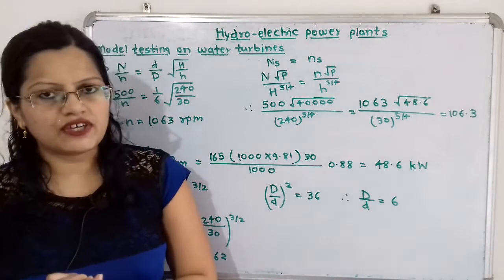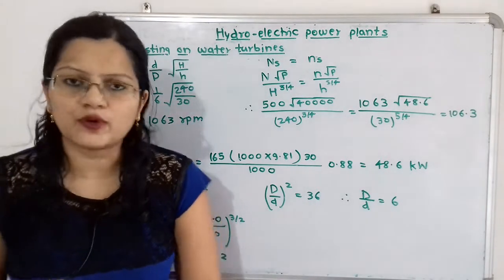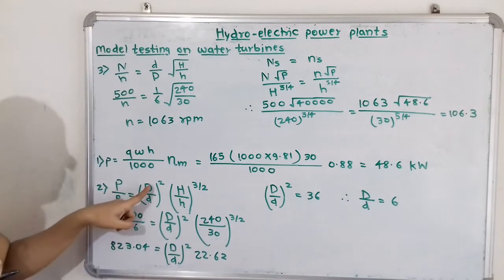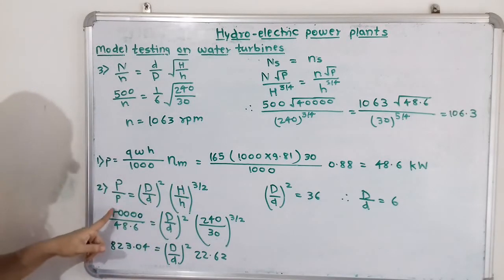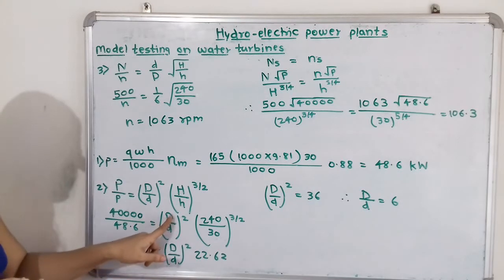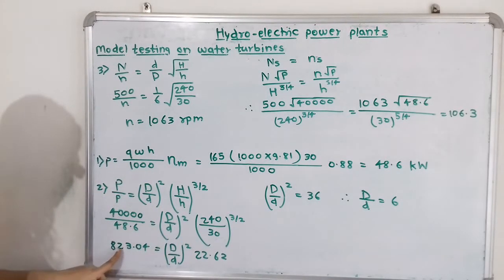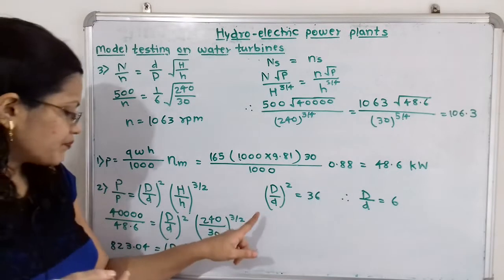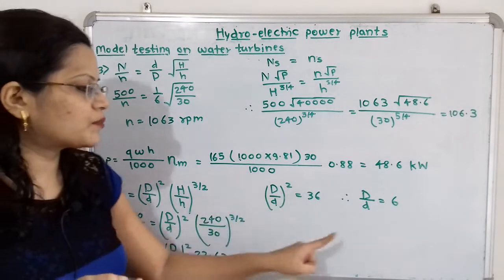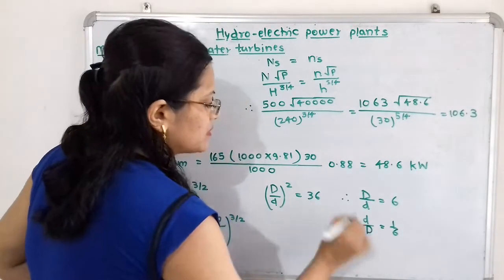Now we calculate the scale ratio — the ratio of the diameter of the model to the diameter of the prototype. The formula is: capital P divided by small p equals (capital D divided by small d) squared, multiplied by (capital H divided by small h) raised to 3/2. Substituting values: 40,000 divided by 48.6 equals (D/d) squared times (240/30) raised to 3/2. This gives 823.04 equals (D/d) squared times 22.62, so (D/d) squared equals 36, and therefore D/d equals 6. Thus the scale ratio small d to capital D equals 1 to 6.